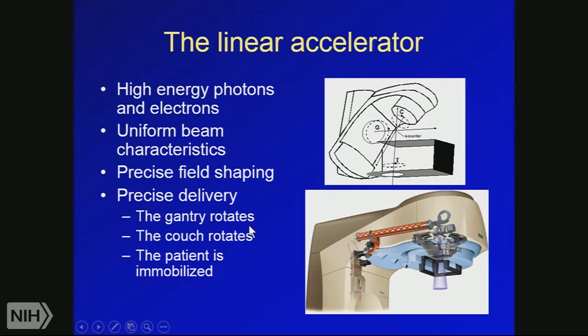They're shaped by what we call different collimators to create various shapes. When the radiation beam exits the machine, it's filtered in a couple different ways so that we have a uniform beam characteristic. That means as you go from side to side of the beam, the X-ray energy is exactly the same. We can do precise field shaping up to about ½ cm now. And then we can have precise delivery, again, with the rotation of the gantry, the couch, and also patient immobilization, which we'll get into in a little bit. So when we do radiation therapy planning, there's really 2 techniques that we now use for radiation therapy planning.